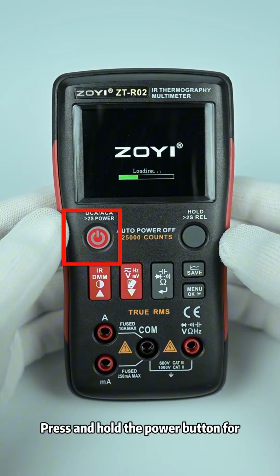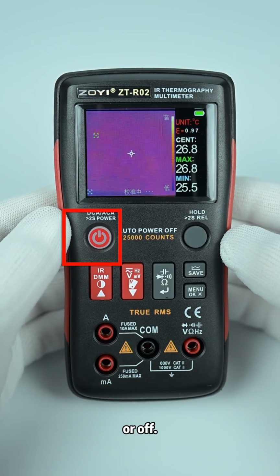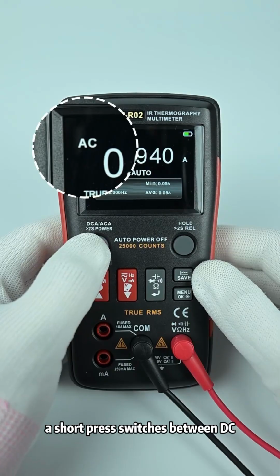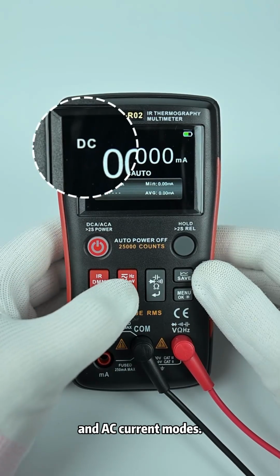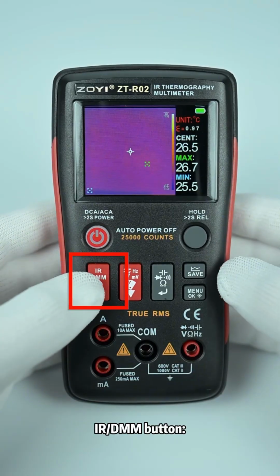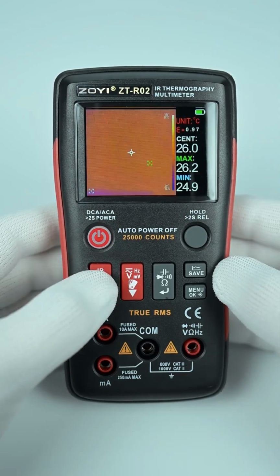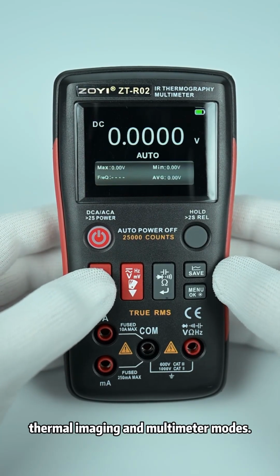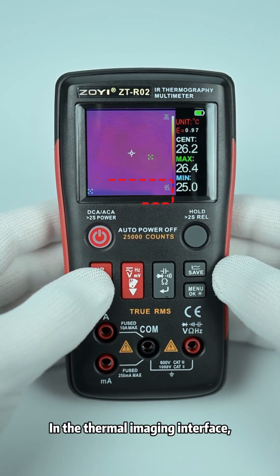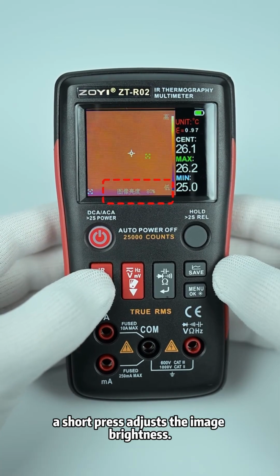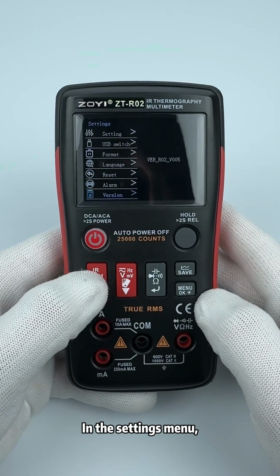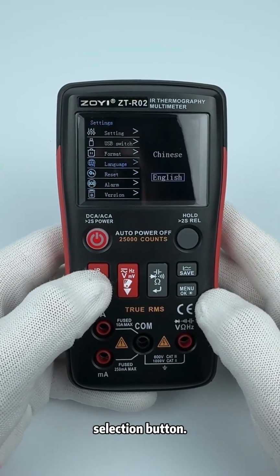Press and hold the power button for 2 seconds to turn the device on or off. In multimeter mode, a short press switches between DC and AC current modes. IRDMM button. This is the core for mode switching. Press and hold to switch between thermal imaging and multimeter modes. In the thermal imaging interface, a short press adjusts the image brightness. In the settings menu, it serves as the increase or up selection button.